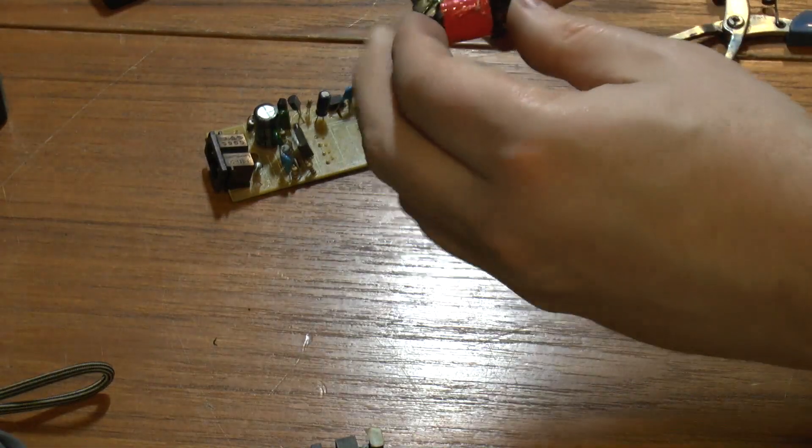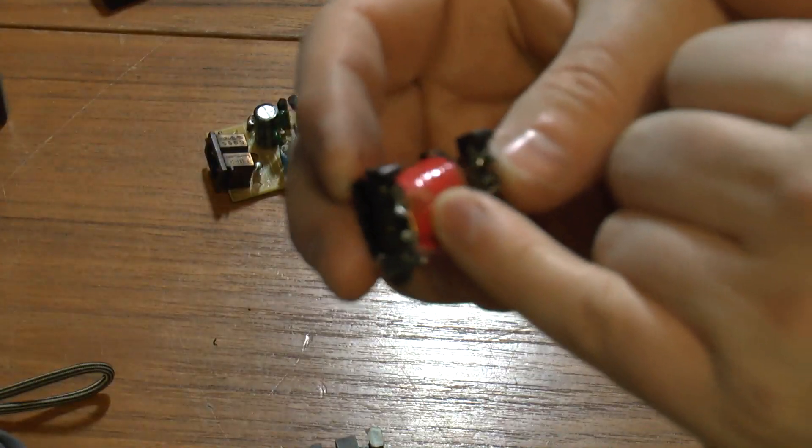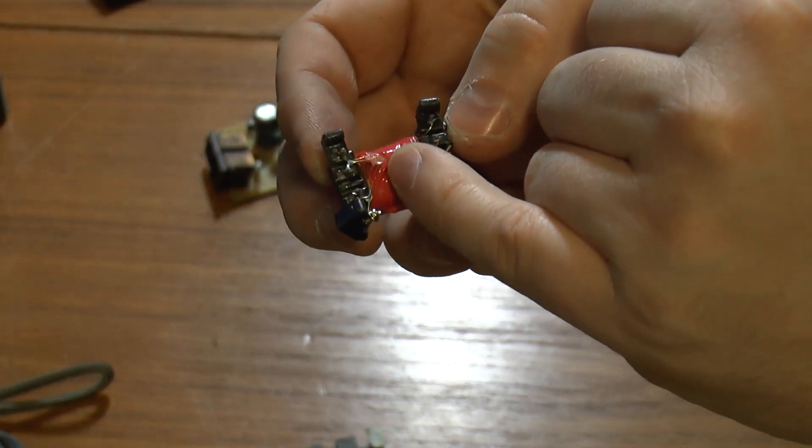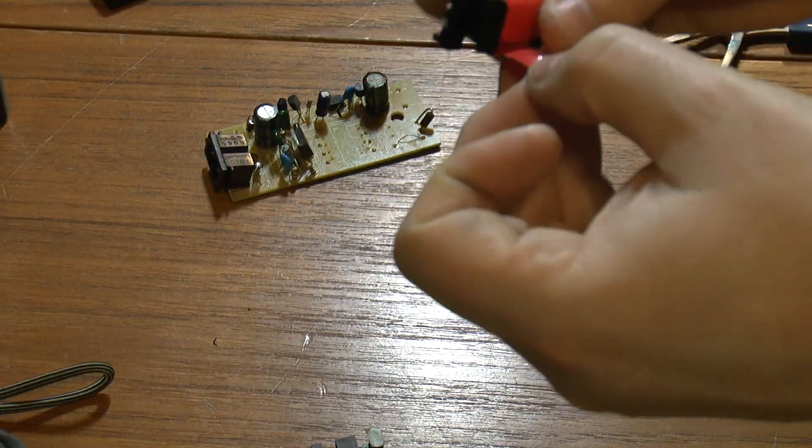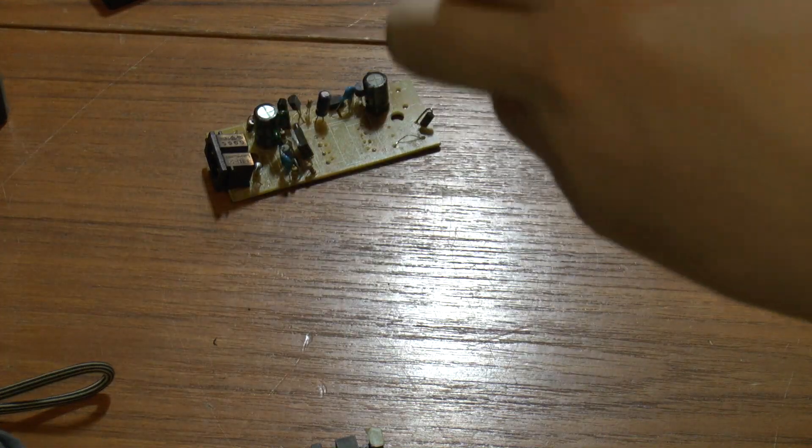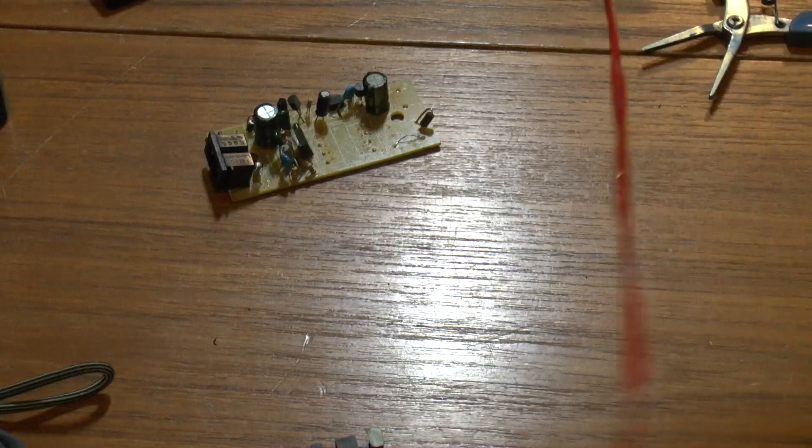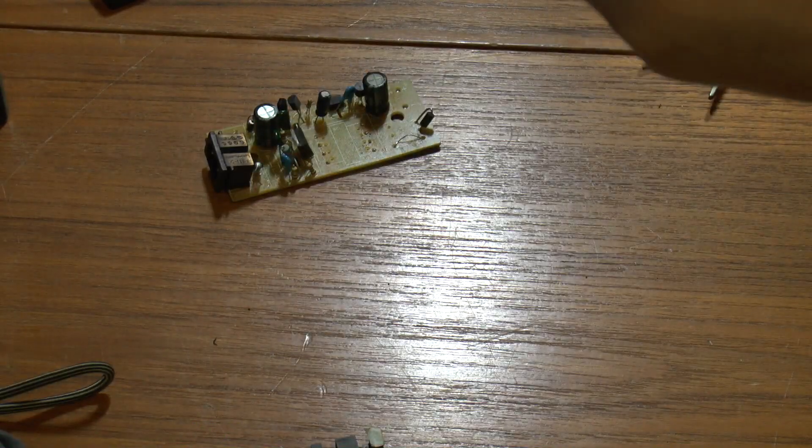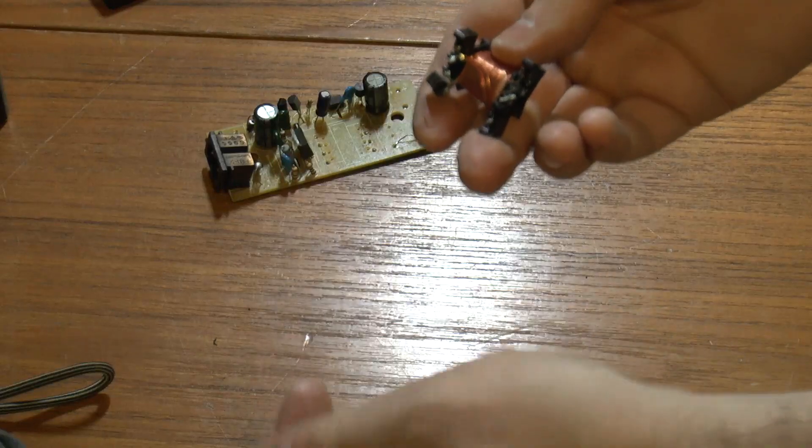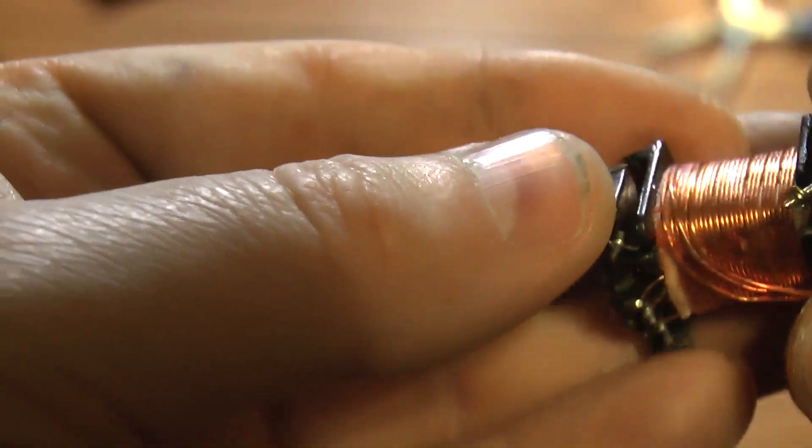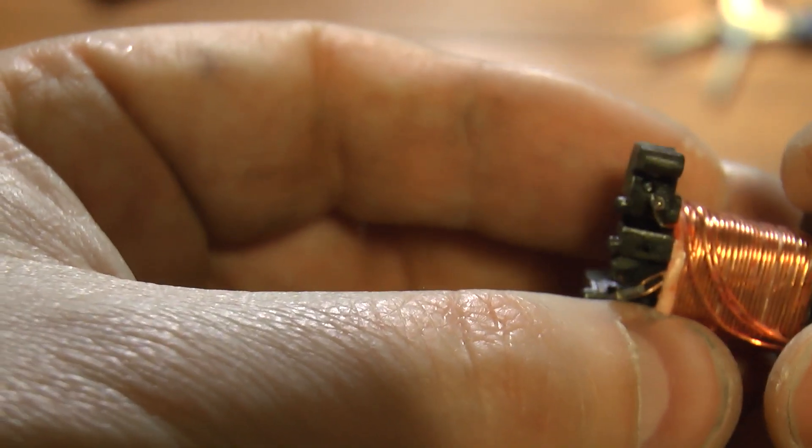Let's see what we've got. Let's count the tape turns, oh I haven't damaged that by the way, that's the insulation as is. That's one, two, three, four, five, six, seven, seven and a half turns of tape on there and here's a close-up of the windings. These are all the primary connections, you can see roughly how far away they are from the secondary.